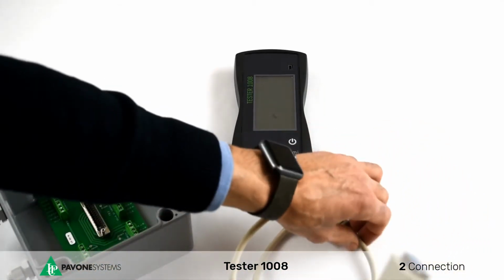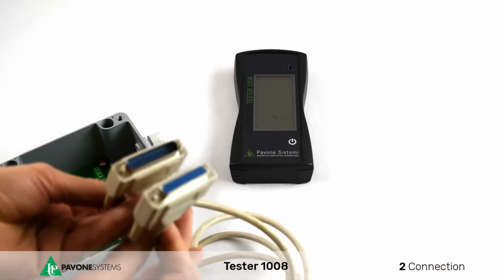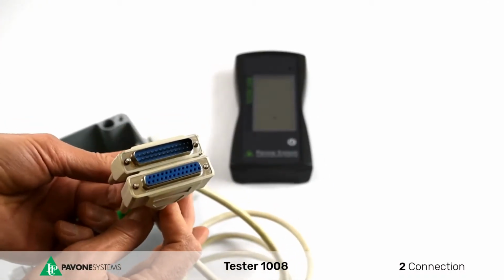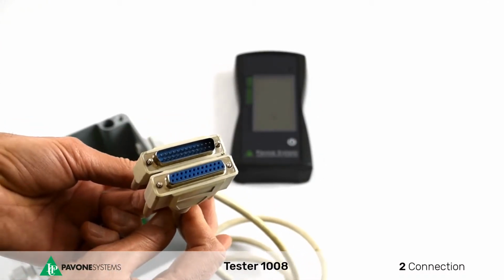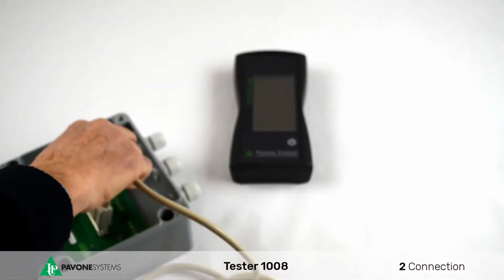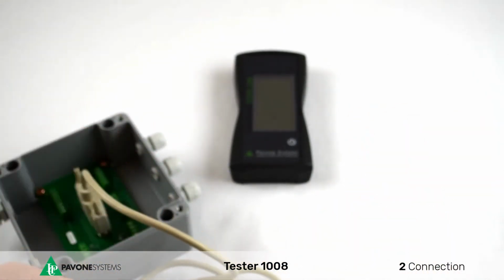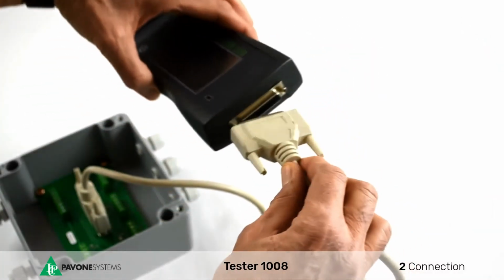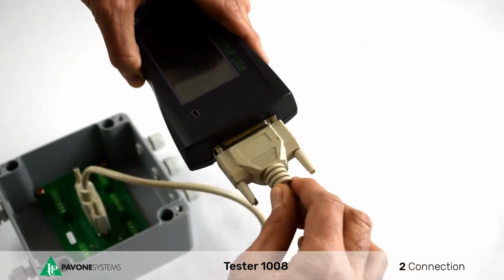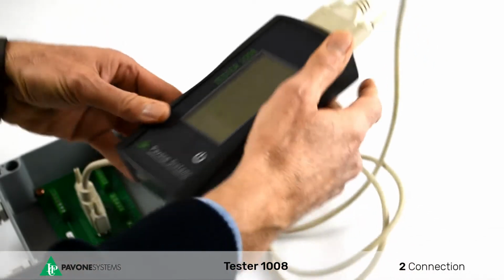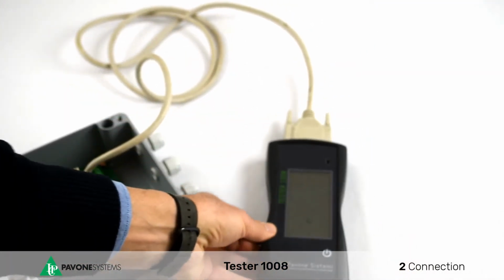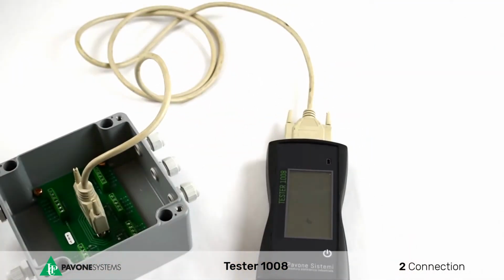There are two kinds of 25-pole connections, male and female. The female cable must be connected to the junction box, whereas the male cable must be connected to the tester. Once the connection has been completed, turn on the weight indicator.